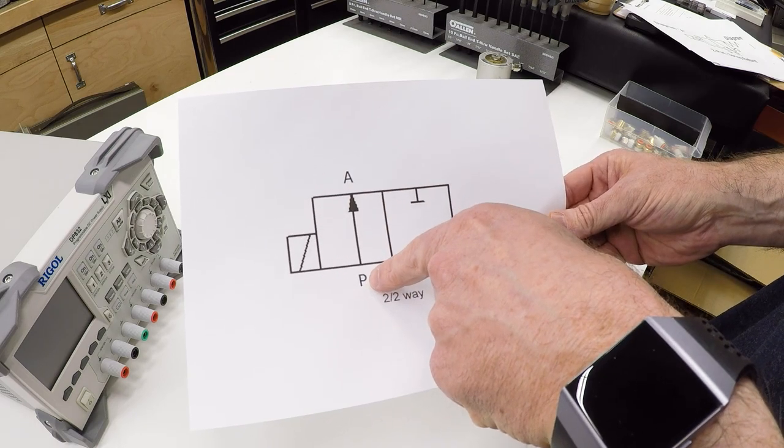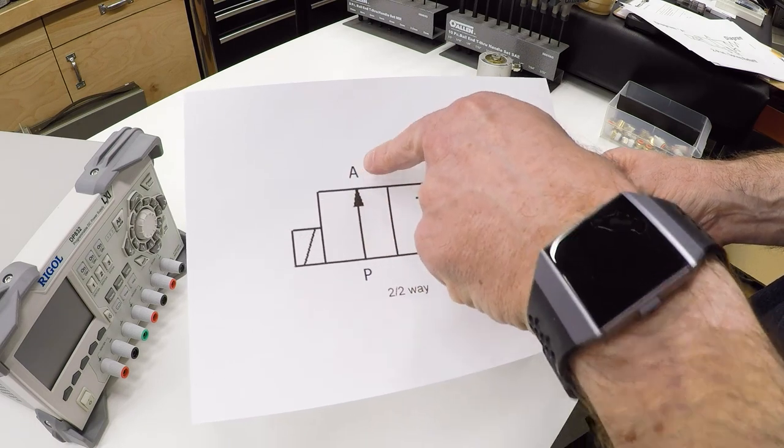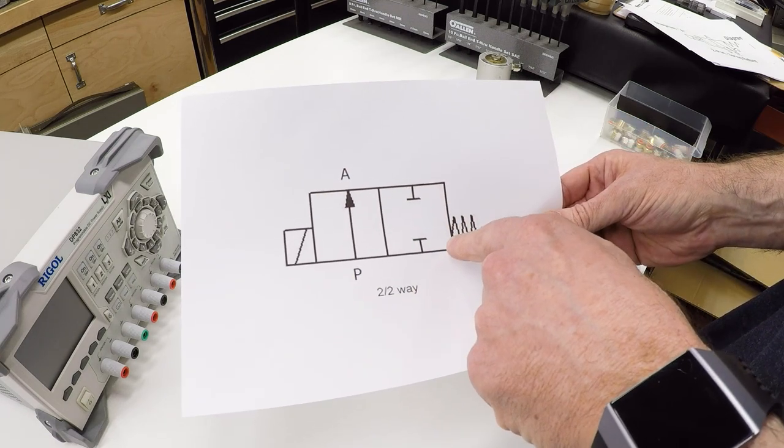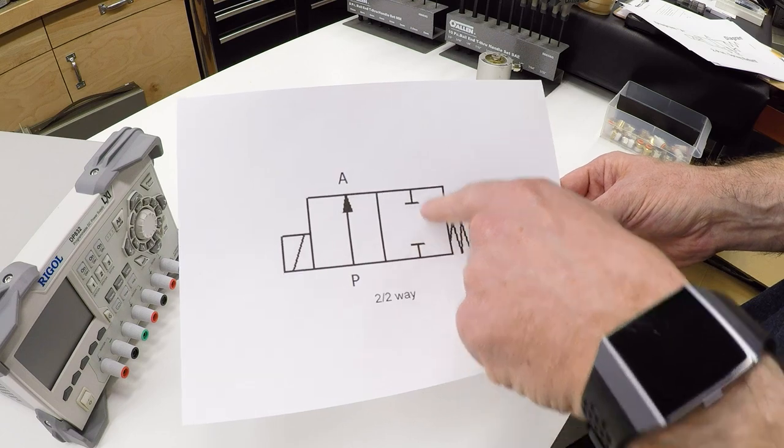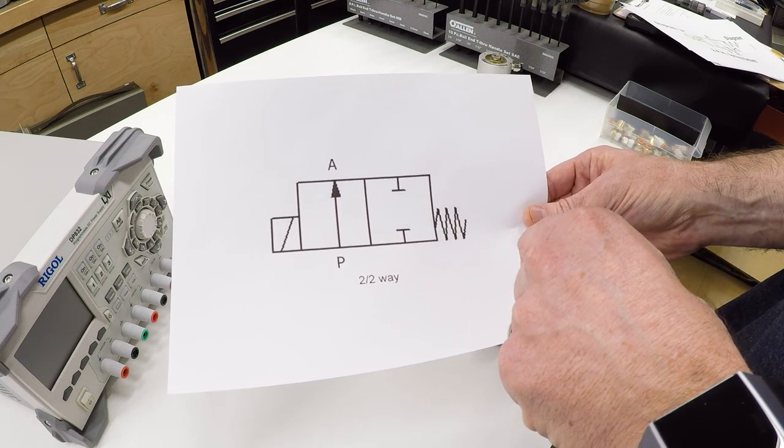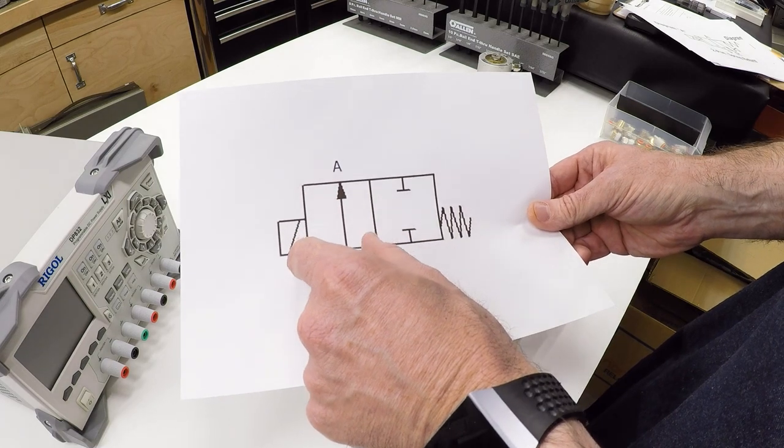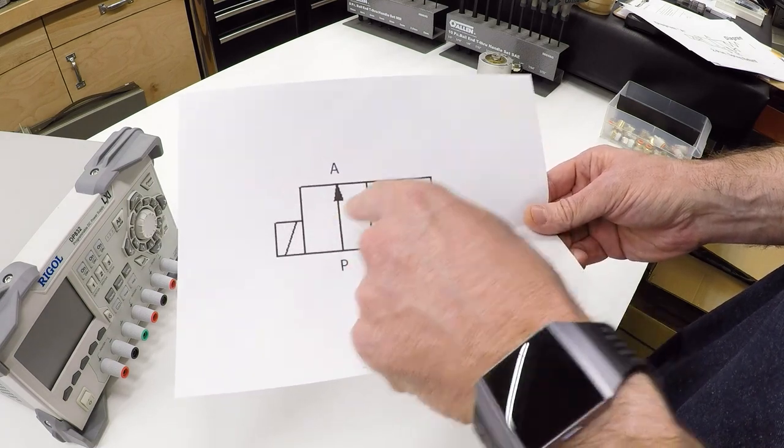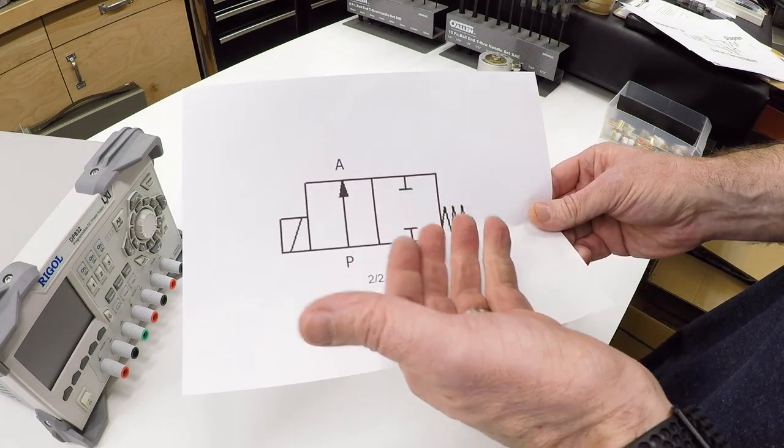This arrow denotes that in this state, the air is allowed to go from the P port out through the A port. In the other state of the valve, it is closed, and both of these ports are blocked. So air can't flow either direction through the valve. You have the two ports and the two different states it can be in, hence a 2-2 valve.